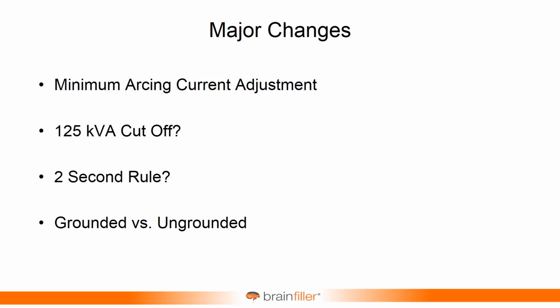And there was also a question about grounded versus ungrounded. Some of you may recall that there was a configuration that you set up your system as either grounded, like a grounded Y, or ungrounded, like a delta, or even impedance grounded, and you got slight differences in your results. And I'm going to talk about how that was addressed with this latest edition of IEEE 1584 as well. There were some big changes made along those lines.